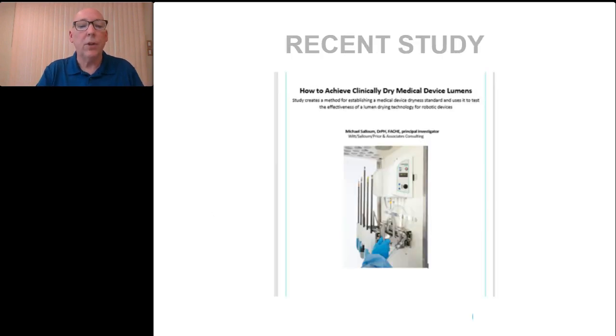Now, there has been a recent study relative to robotic devices and drying those devices. This study was commissioned to determine the effectiveness of a novel lumen drying system and its directed airflow process for drying reusable medical device lumens, such as robotic devices. The study assessed whether the internal channel surfaces of robotic arms connected to the system reached a consistent, measurable standard of dryness in a predetermined amount of time.